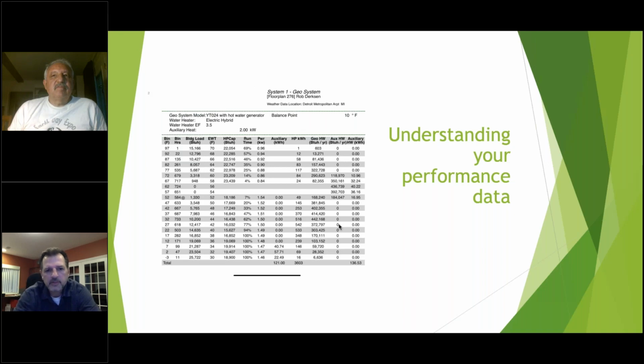Now, geothermal can be sized to 100% of the load, and the most extreme temperature that the state of Michigan, or any state in the country really, could throw at us. But it's not economical to do that. The cost of oversizing a system and the additional piping needed in the ground loop would far offset any consumption savings in power.